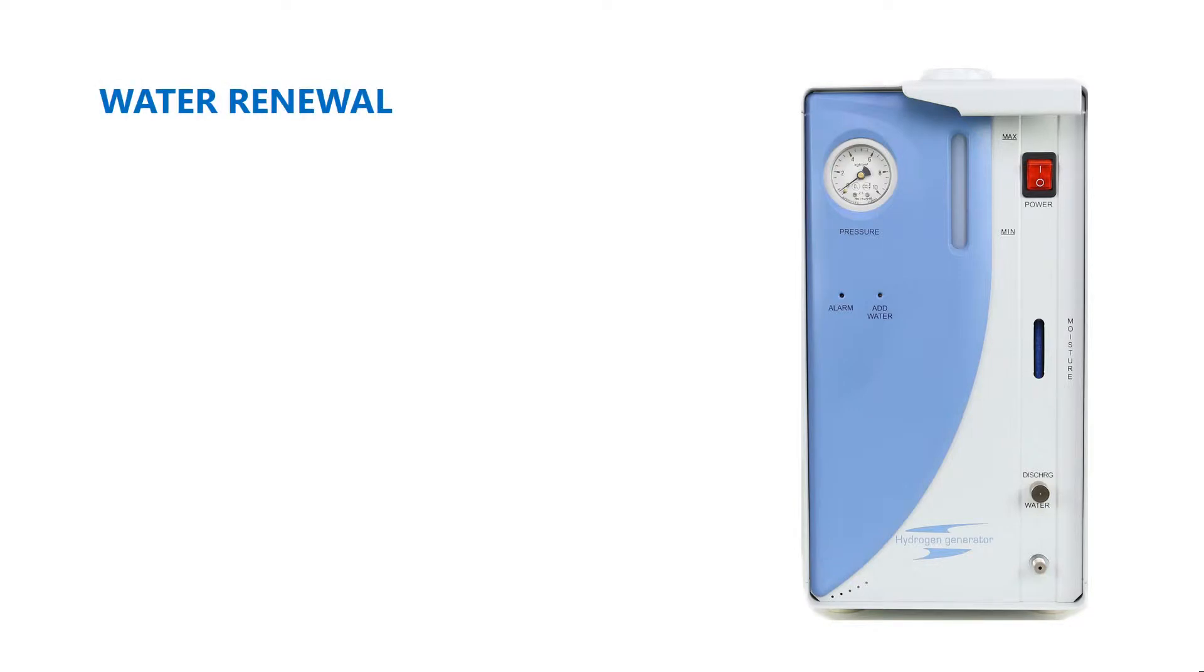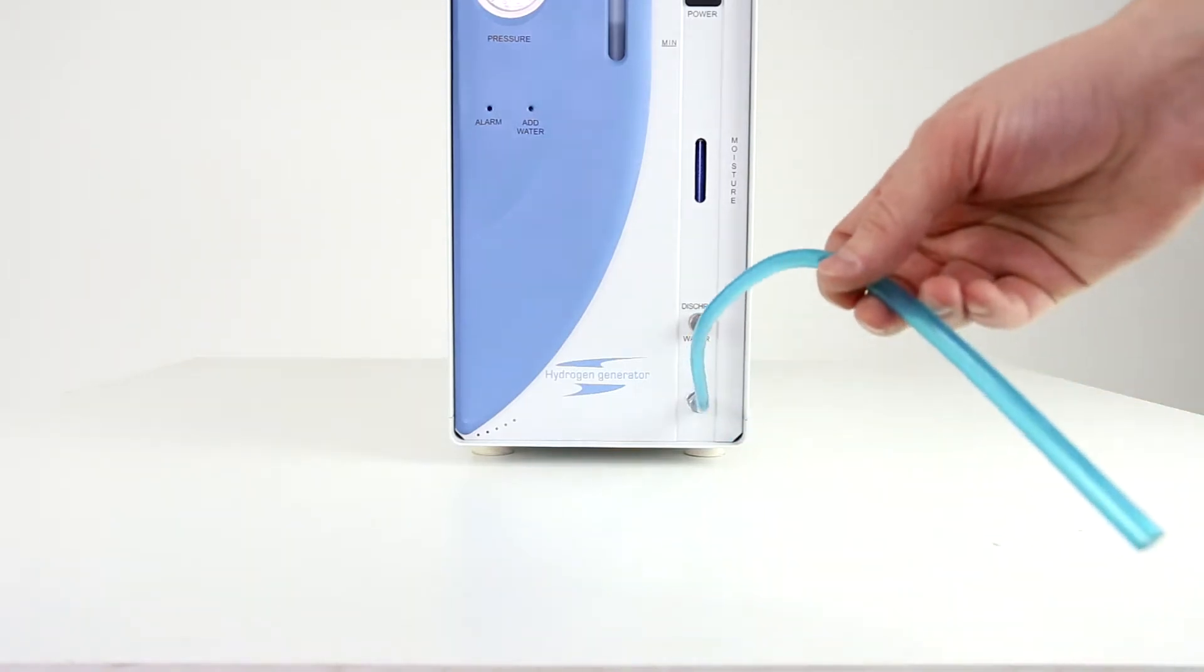Water renewal: Frequency once a week, and on the occasion of long breaks in work, more than a week. To easily drain water, use the tube supplied with the generator. Prepare a container to drain water and unscrew the drain valve. Drain all water. Tighten the drain valve.